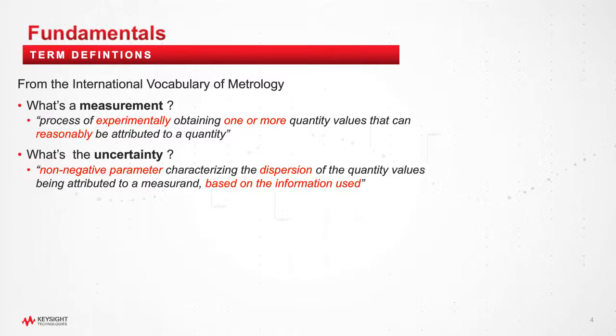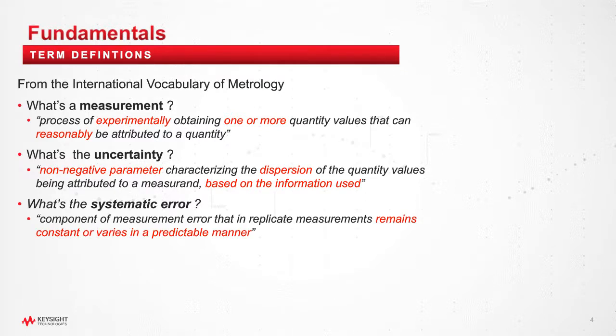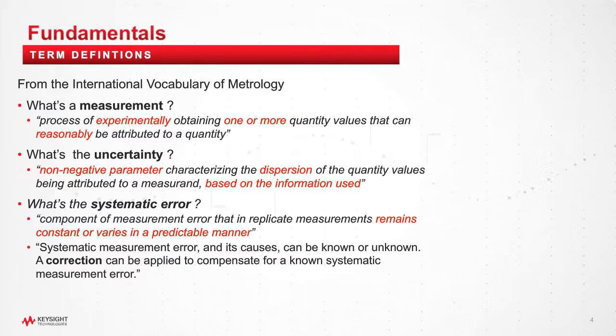Now, there is another fundamental part which is many times confused with uncertainty, which is called systematic error. What's the difference between systematic error and uncertainty? Well, the systematic error is the component of the measurement error that in replicated measurements remains constant or varies in a predictable manner, which means that a systematic measurement error can be corrected. And so a correction can be applied in order to compensate for the systematic measurement error, while you cannot compensate for the uncertainty. The uncertainty is what it is, while the systematic error can, under certain conditions, be corrected for.